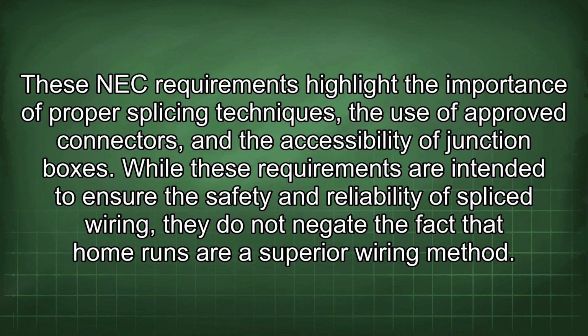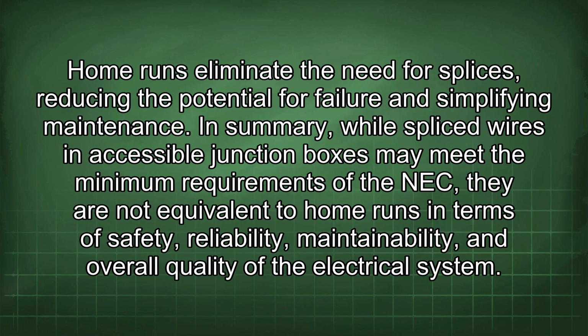These NEC requirements highlight the importance of proper splicing techniques, the use of approved connectors, and the accessibility of junction boxes. While these requirements are intended to ensure the safety and reliability of spliced wiring, they do not negate the fact that home runs are a superior wiring method. Home runs eliminate the need for splices, reducing the potential for failure and simplifying maintenance. In summary, while spliced wires in accessible junction boxes may meet the minimum requirements of the NEC, they are not equivalent to home runs in terms of safety, reliability, maintainability, and overall quality of the electrical system.